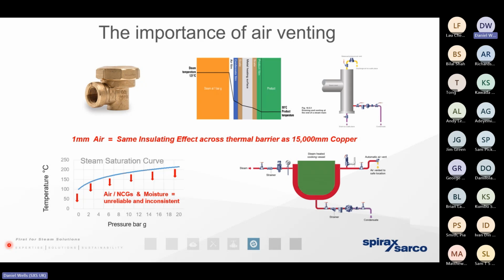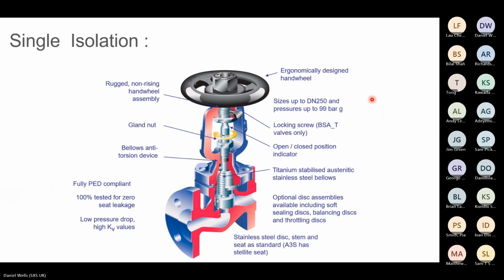At the very, very end of every distribution network, the air is going to rise to the high point, the condensate is going to fall to the low point, and then at the occasional high point, for example, if that pipework needs to rise to climb over an infrastructure, that's where we want to position that air vent to make sure that we don't have a bubble of air that's trapped that could result in an inefficiency.